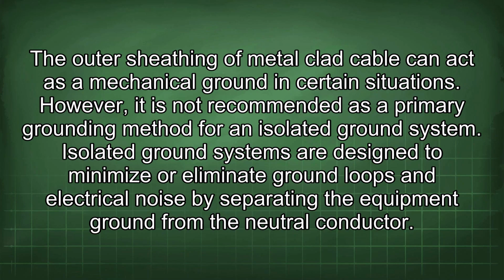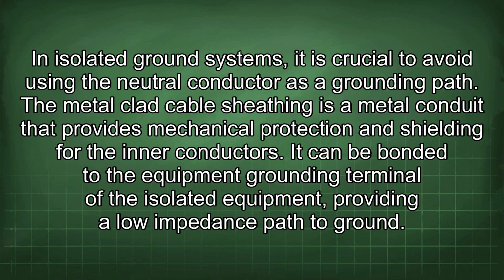The outer sheathing of metal-clad cable can act as a mechanical ground in certain situations. However, it is not recommended as a primary grounding method for an isolated ground system. Isolated ground systems are designed to minimize or eliminate ground loops and electrical noise by separating the equipment ground from the neutral conductor. In isolated ground systems, it is crucial to avoid using the neutral conductor as a grounding path.